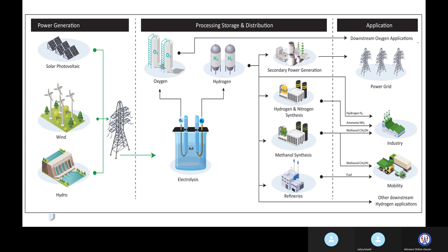The fourth one is your substation, or switch yard, because we require a bulk amount of power, megawatt power. This power comes from the grid at high voltage level, 132 or 220 kV, and then is stepped down to 33 kV and 11 kV. This stepped down power goes into this area, where you see numbers of transformers - this area is called the rectifier area. From here power goes at 33 or 11 kV, and the rectifier transformer converts this into low voltage 440 volts.